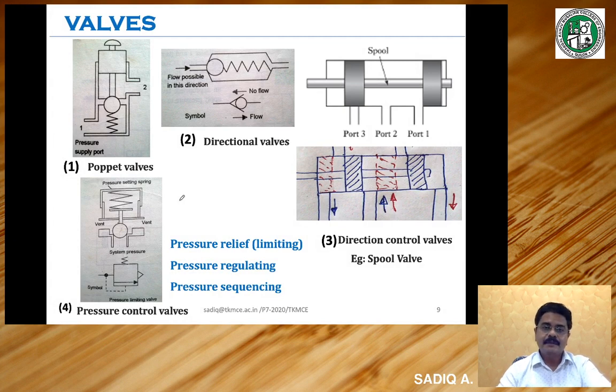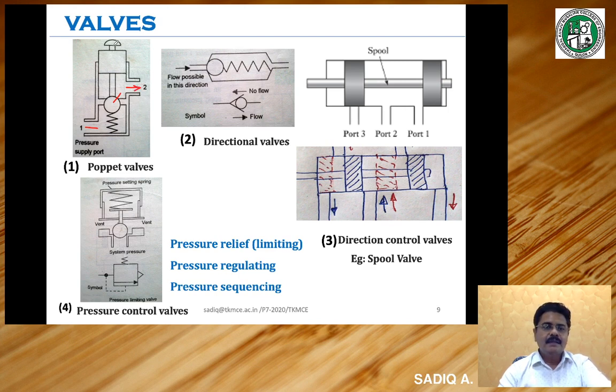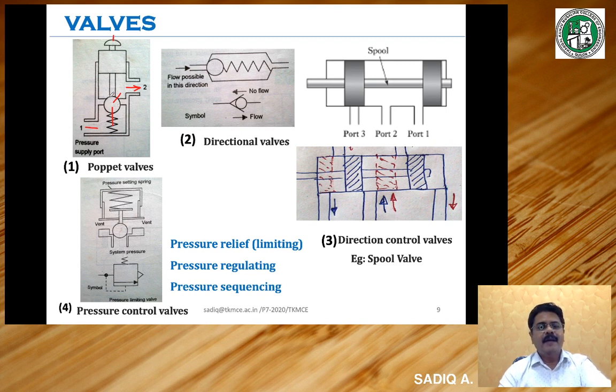Let us see examples of valves. The first is a poppet valve. It has a body, a push button connected to a ball valve via a rod, and a spring. The fluid can enter through an inlet port but is blocked. When you push the button from the top, the ball is pushed down against the spring load, creating an opening so fluid escapes through the exit port. When the force is released, the ball returns to its seat and flow is blocked. The poppet valve acts as a one-direction valve — flow occurs only when pressure is applied.